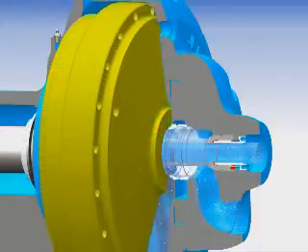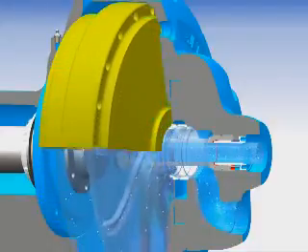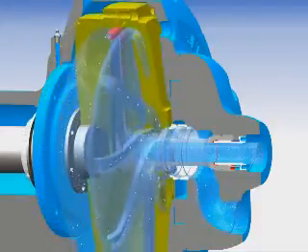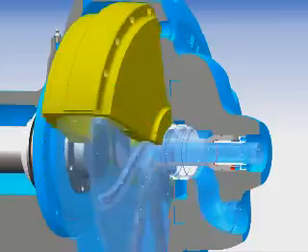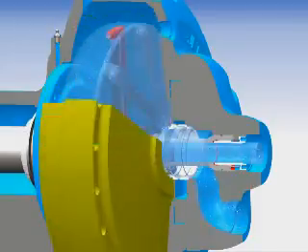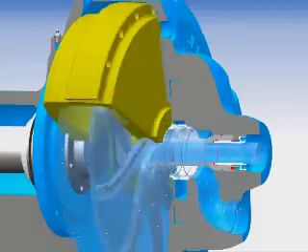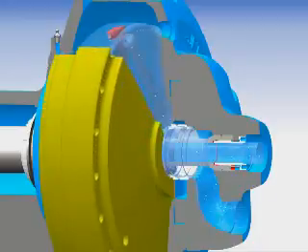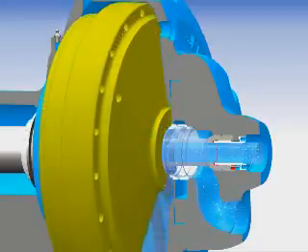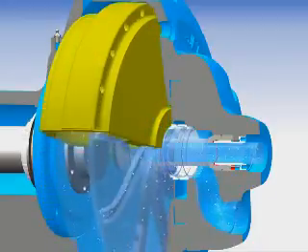The Roto-Jet can change pressure by adjusting speed, change capacity by changing the pitot tube size, and purge itself of air on start-up.